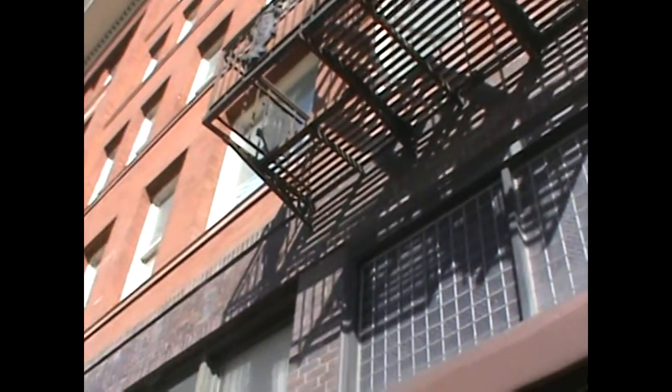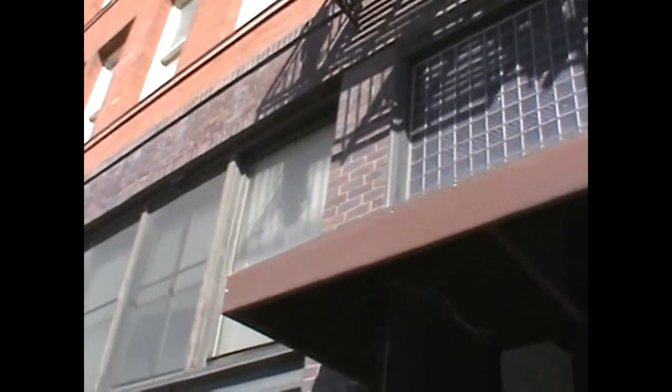But these people are going to get all trapped. So the 20, 30, 50 people that finally come to the end, who's going to fall through here or jump through here in case there is a fire? They're going to bounce on this and then fall here. But let's say it's missing its ladder. It could be a pre-existing non-conforming. Is it a life safety issue, or is this a special building or a dangerous building? The fact that now nobody can self-evacuate without help, I'd say it's a dangerous building at this point.